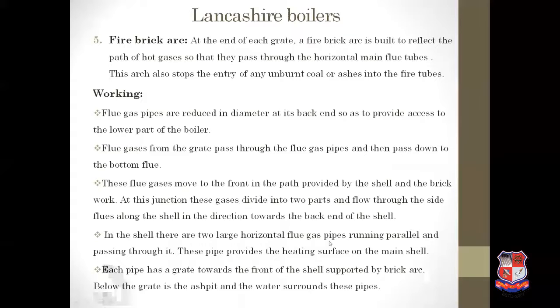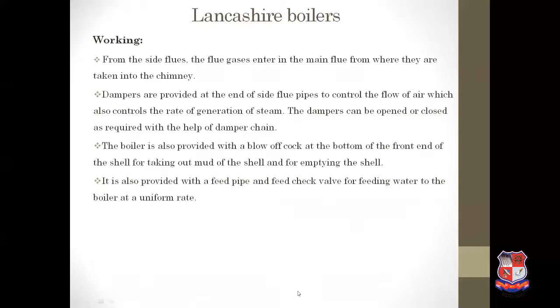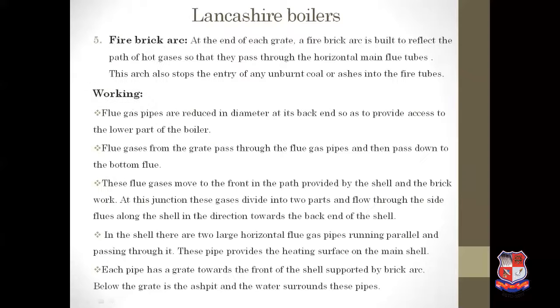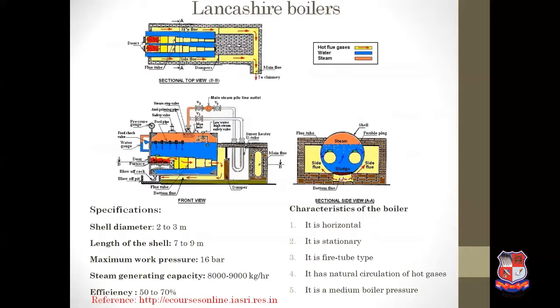In the shell, there are two large horizontal flue gas pipes running parallel through it, providing a heating surface. Each pipe has a grate towards the front end supported by brickwork, with an ash pit below the grate and water surrounding the pipes. From the side flues, the flue gases enter the main flue from where they are taken into the chimney and released into the atmosphere.